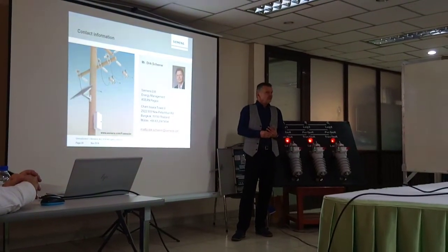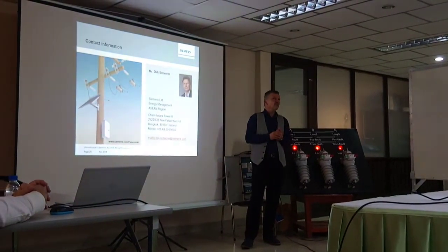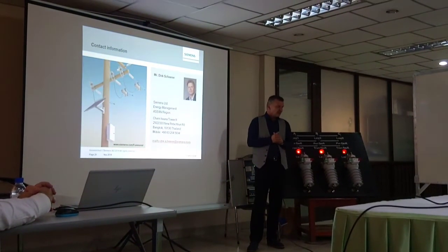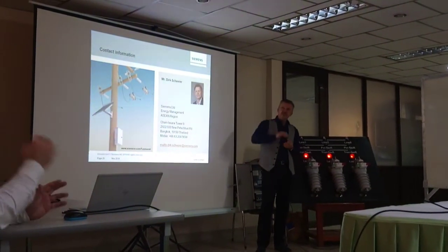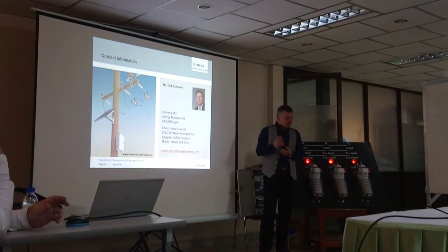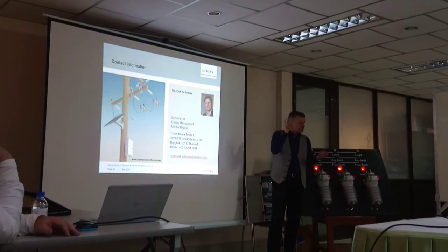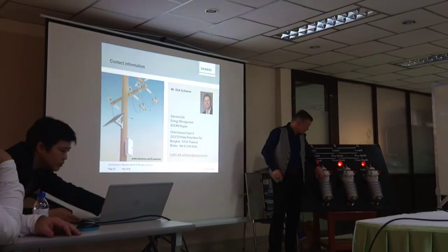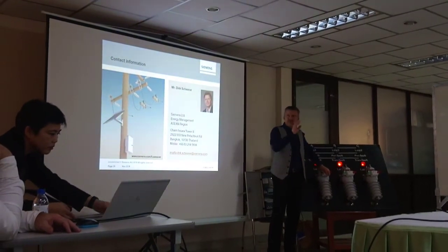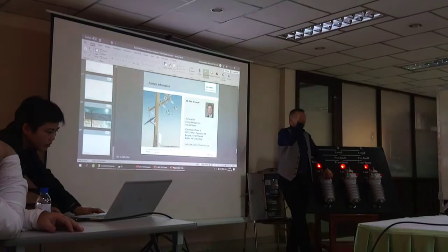Actually, if you want to use a fuse as a link or something like that, we recommend using a solid link, because we have seen it in Thailand. They have a big fuse, we have 5 amp or 10 amp fuse settings, and then we have a 40 or 50 amp fuse in series with that one, just as a link.